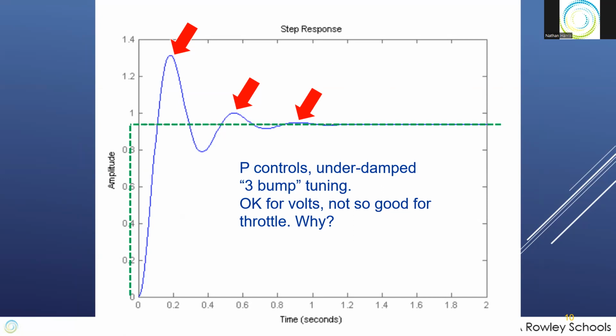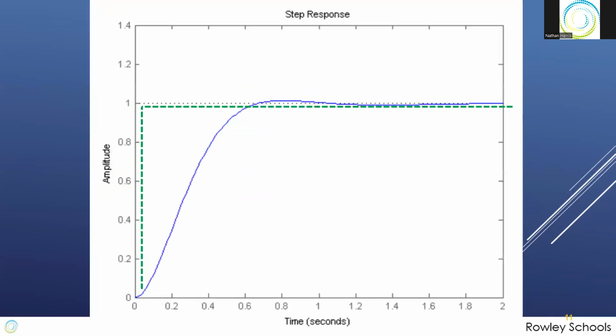But when you're talking a fuel regulator, the fuel system and mechanical side of a generator, that may not be so good, right? Mechanical flexing of the coupling, bang, bang, bang, back and forth, can cause problems. So this 3-bump tuning, we used to call it, actually is a term for it. We used to set up excitation regulators at small steam turbines. By doing this, we turn them up and watch the needles swing 3 times, and we disturbed it. So it was okay to do that with voltage, but not with throttle or fuel.